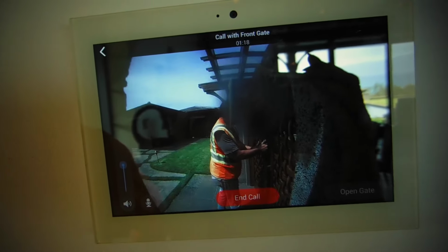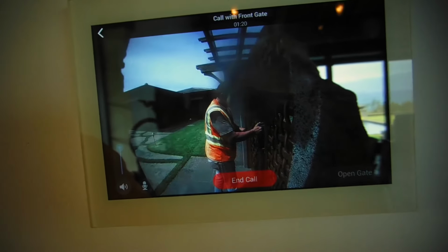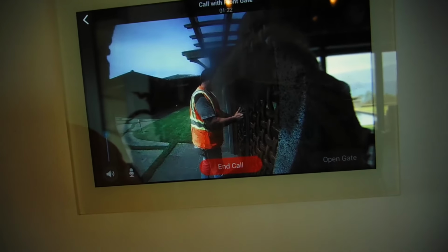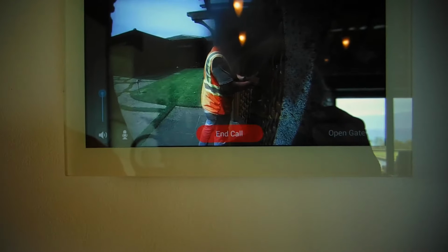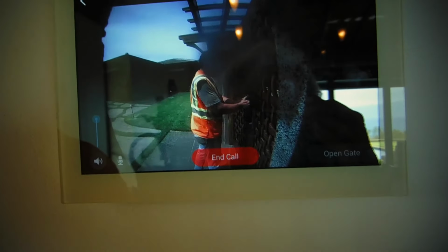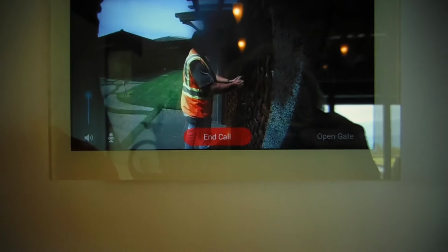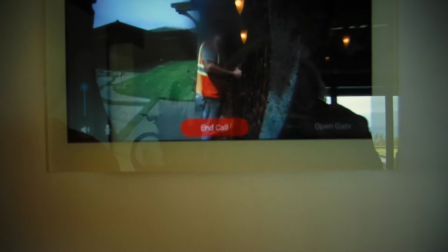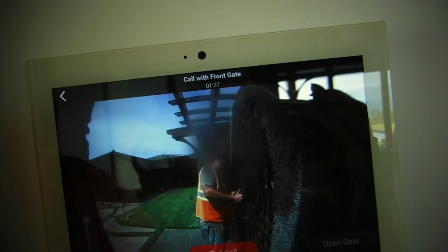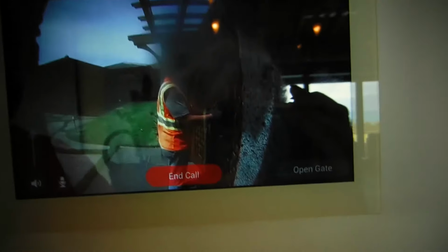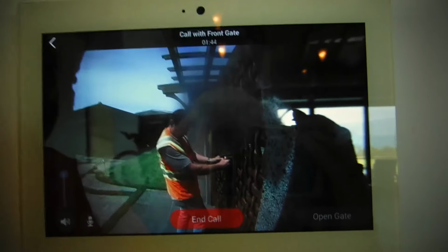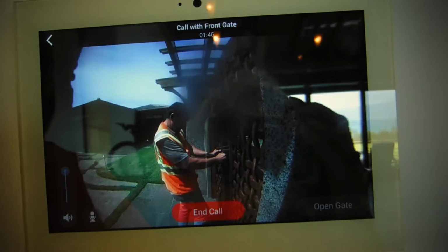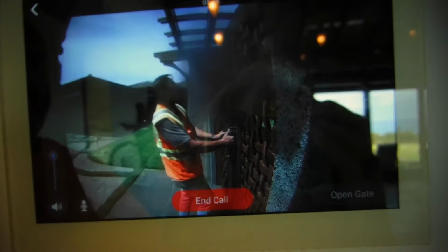So if you have a lot of pressure on that lock, if that door isn't sitting at neutral, like if you don't have the pin dropped on the second door, the functionality is going to be a little weird, because if you have pressure on that pin, then it can't lift when the magnet hits. So you need to drop the pin on that second door so that it's fixed in place. Oh, that's not good. Yeah, you need to set the pin on that second door.